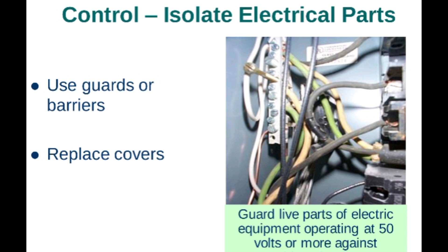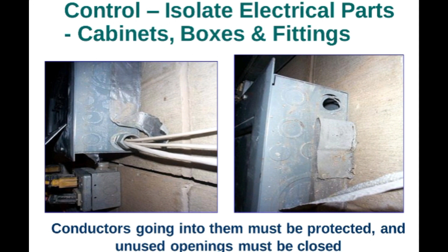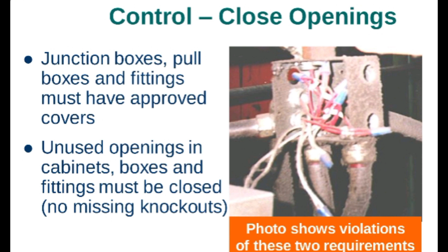Control: isolate electrical parts, cabinets, boxes, and fittings. As you can see in this observation picture, conductors going into them must be protected and unused openings must be closed. Control: close openings. Junction boxes, pull boxes and fittings must have approved covers. Unused openings in cabinets, boxes and fittings must be closed. No missing knockouts. As you can see in this picture, the photo shows a violation of these two requirements.